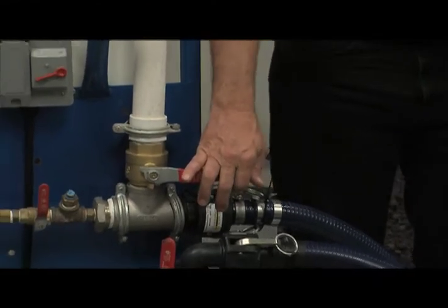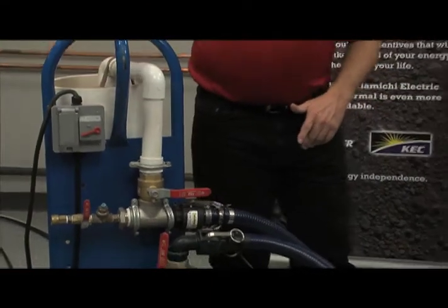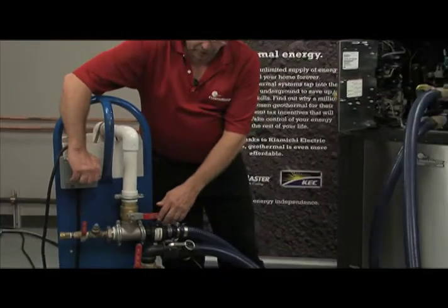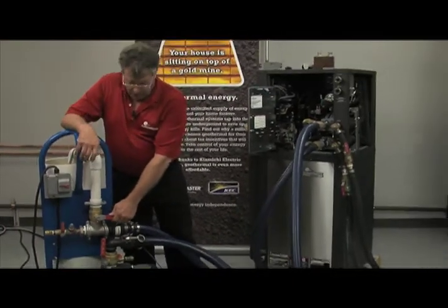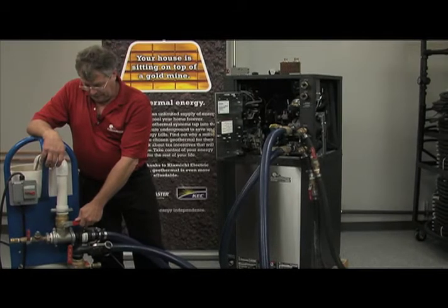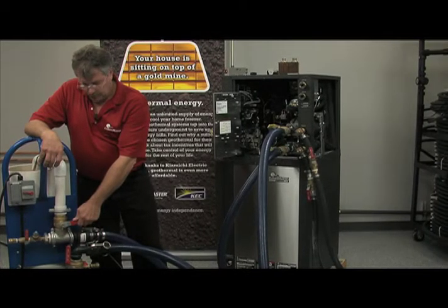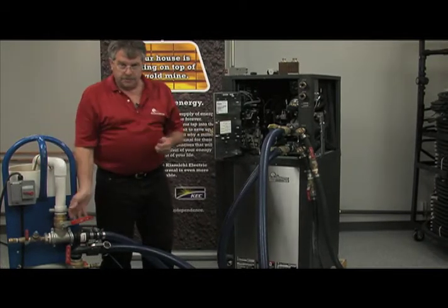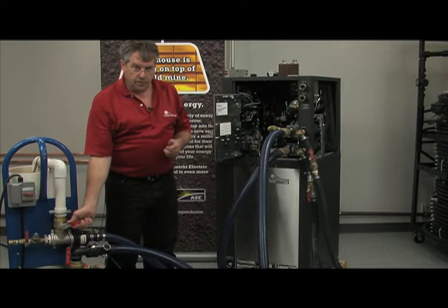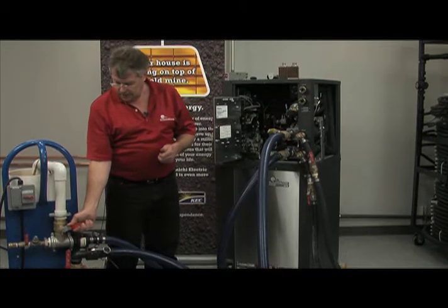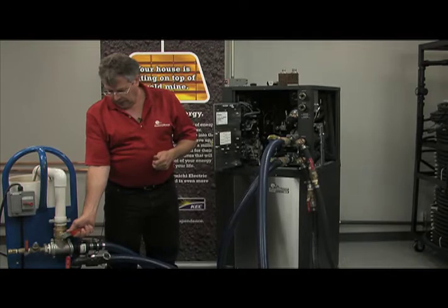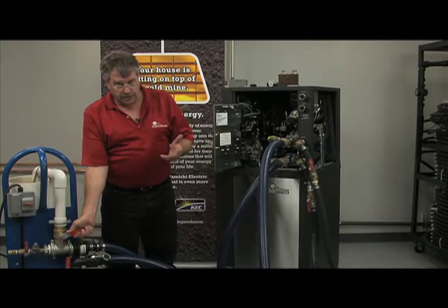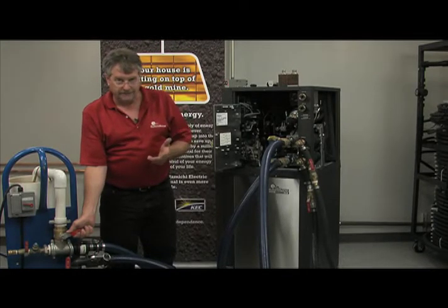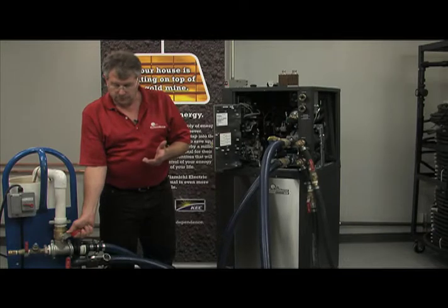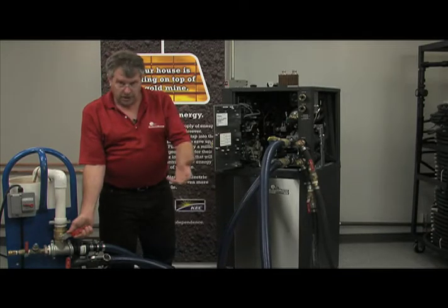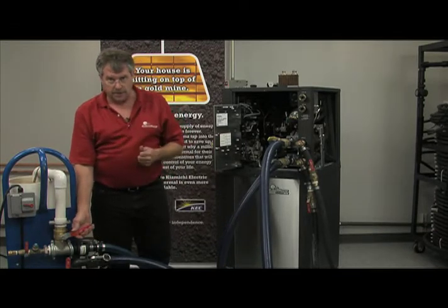So we're going to go ahead and turn the pump on. Again, our return valve is fully closed at this point, so we're going to power the pump on. Slowly open up this valve to again manage the flow going through our flow sensor and the heat exchanger. We can open that thing up again slowly, getting up to about 25–30% of the throttle. You can hear that air being dislodged coming back into the flush cart.